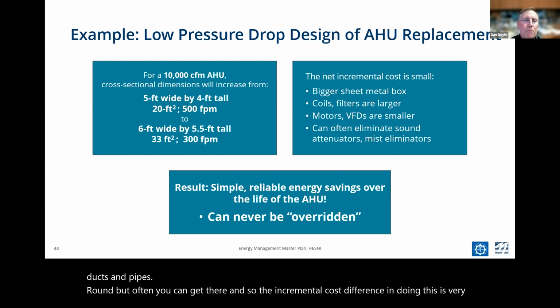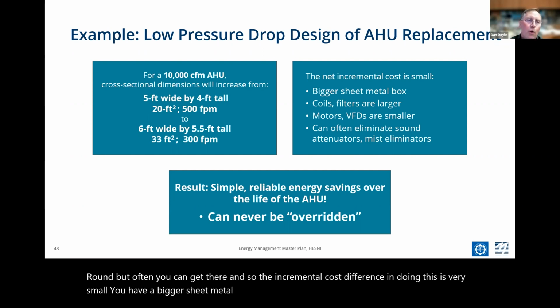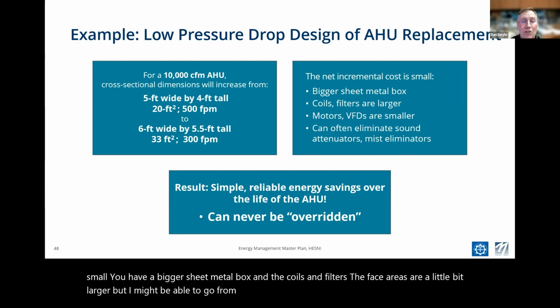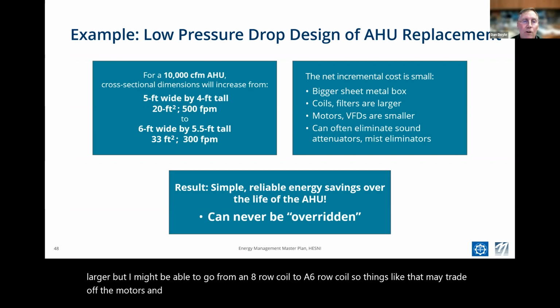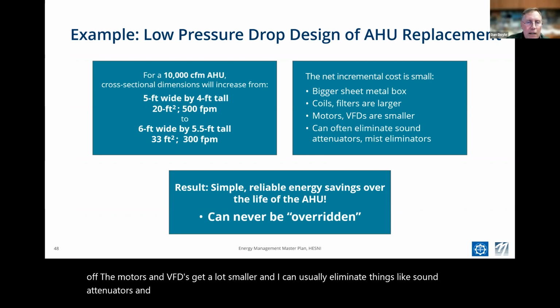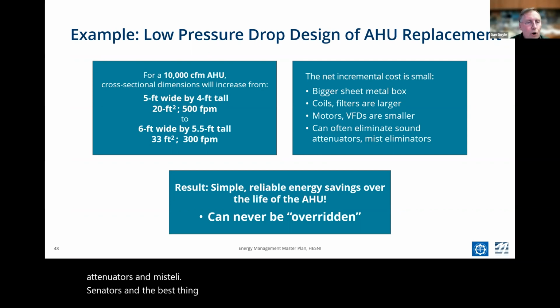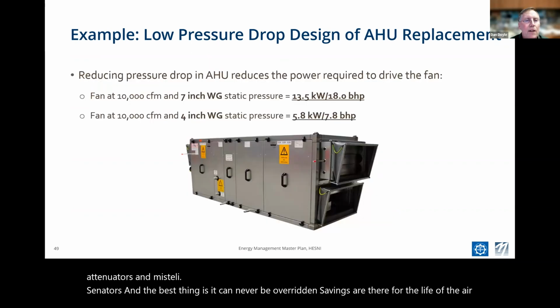You have a bigger sheet metal box, and the coils and filters, the face areas, are a little bit larger, but I might be able to go from an 8-row coil to a 6-row coil. So things like that may trade off. The motors and VFDs get a lot smaller, and I can usually eliminate things like sound attenuators and mist eliminators. And the best thing is it can never be overridden. Savings are there for the life of the air handler, 25 years.